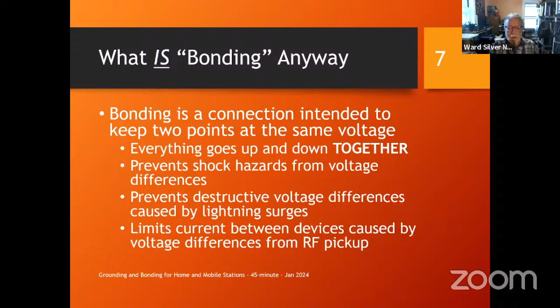And for bonding to work, it has to be a low impedance, electrically short connection across the frequency range that you're working with. That could be AC, it can be lightning, which is the low AC all the way up to a megahertz or more, and then RF that we use, which is down in the medium frequency range all the way up into UHF and microwave. So you want it to be short so that it doesn't start acting like an antenna or a transmission line, and it has to be low impedance. That's low X and low R for bonding to work. Now, the different ranges emphasize resistance or inductance. We'll get into that. It also has to be heavy enough to carry the expected current.